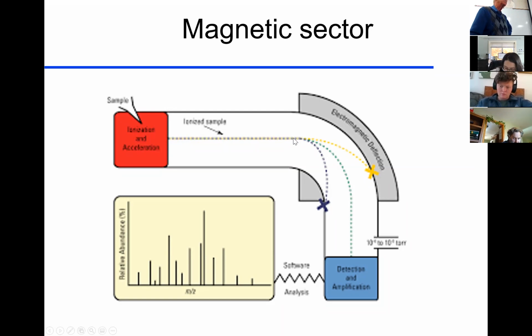Right now, this is a complete mixture of all my bits and fragments. Now, if I put that into a magnetic field, there's a right-hand thumb rule that says an electrical charge moving through a magnetic field will have a force exerted in this direction. That magnet has a very low current originally when we start the process, and that focuses your lowest molecular weight mass around the curve.